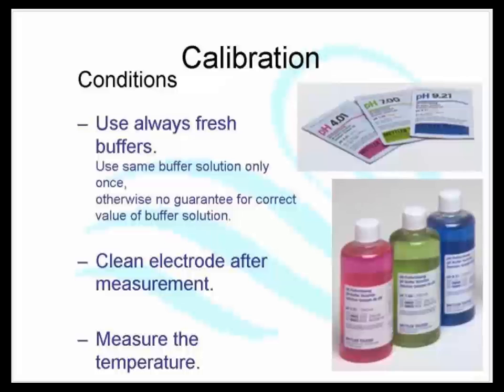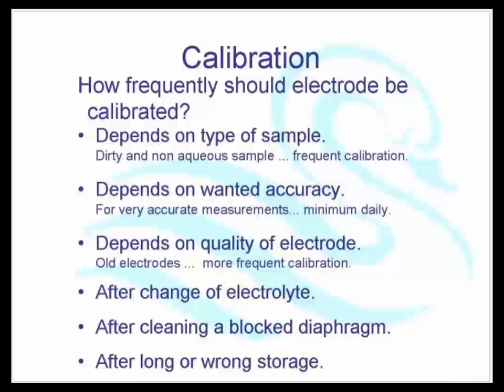Now, calibration of pH probes. How frequently should the electrode be calibrated? Before we get into this, what I need to tell you is the pH probe was designed for use in a lab. It was for use in a lab where you'd get a little lab technician wearing a white coat who would love it and tend it and look after it and clean it and calibrate it every day. It was never ever designed to be used in the field. It is not rugged enough to be used on a mine site or an oil rig or in the field.